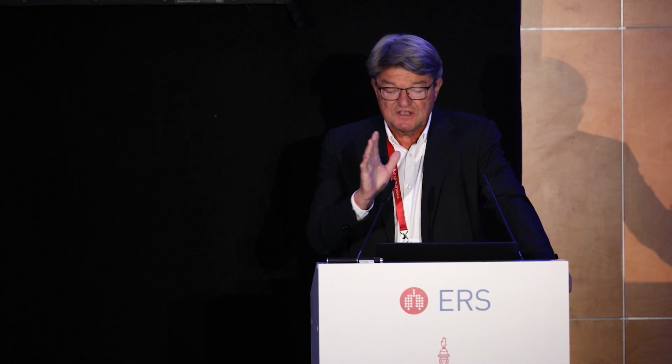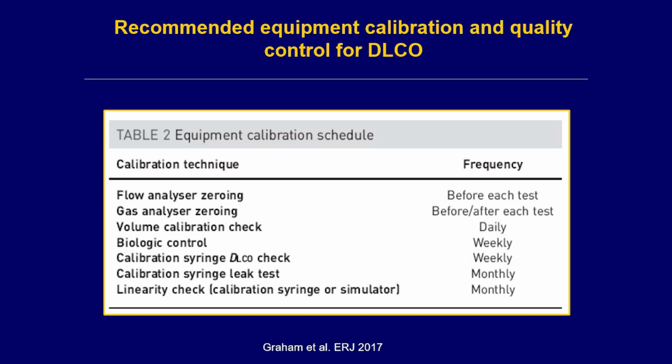Now, these are the things we have to be aware of if we should trust our measurement. The flow analyzer must be zeroed. The gas analyzer must be put on zero.